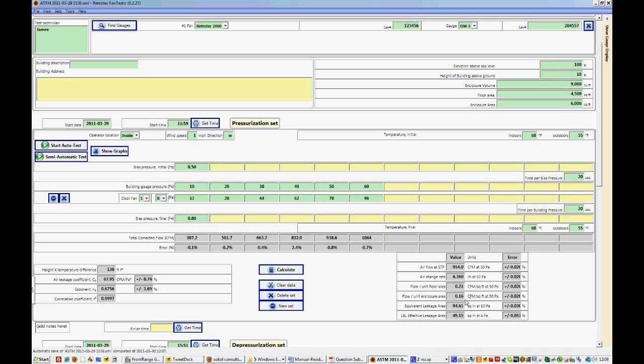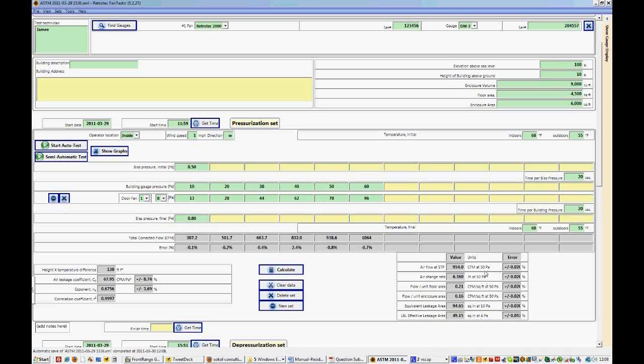And then we have an equivalent leakage area in square inches at 10 pascals and an effective leakage area in square inches at 4 pascals. Now you'll notice that we did not start the test at 4 pascals. And the reason that we can derive this result at 4 is because we use this equation to extrapolate back to 4 pascals. And we can do that to extrapolate forward as well. So if we wanted a CFM at 75 for instance, we could achieve that using the equation.